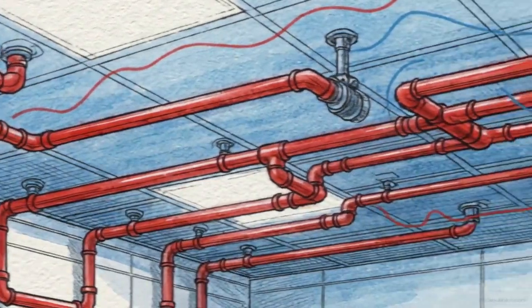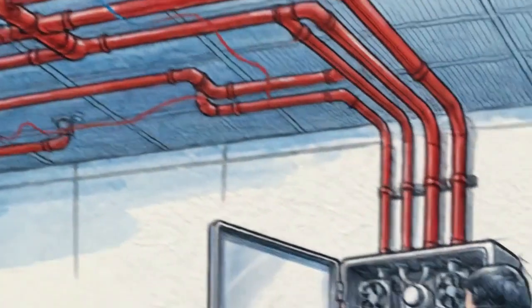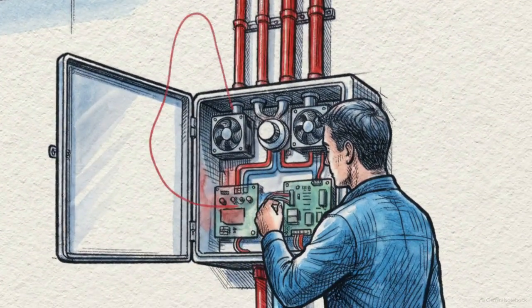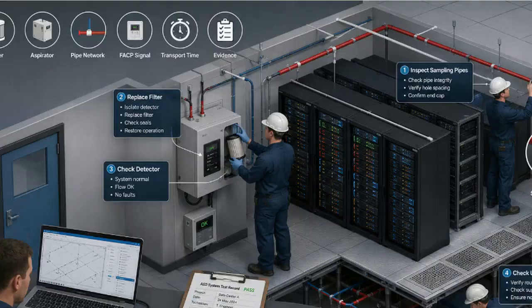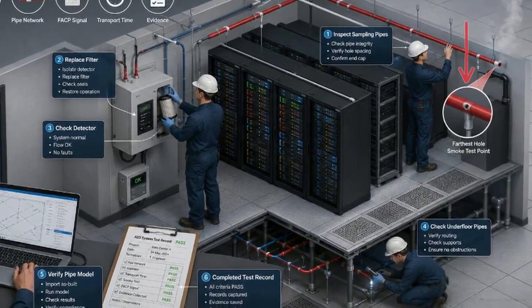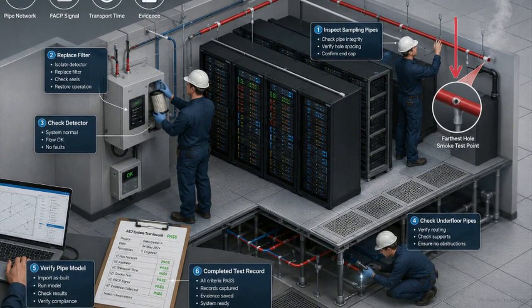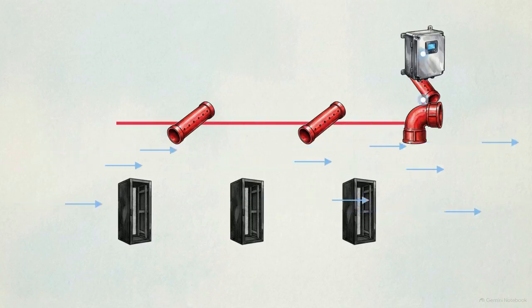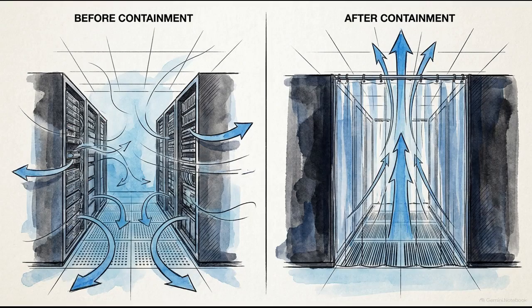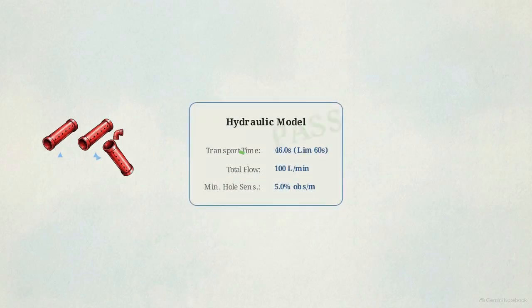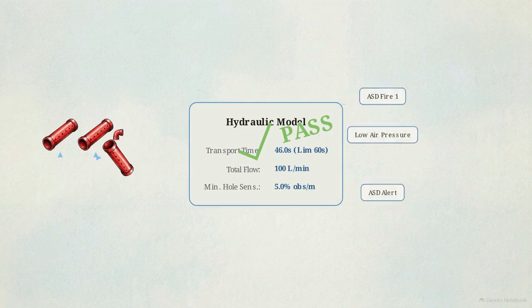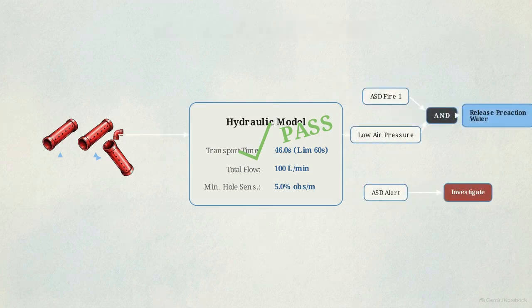Maintaining an ASD system requires a comprehensive inspection, testing, and maintenance program that evaluates the entire sampling network, not just the particulate filter. This holistic maintenance workflow includes verifying pipe integrity, simulating flow faults, and conducting routine transport time tests from the farthest sampling hole. Operators must treat ASD as a living network. Any facility modification that changes the room's airflow velocity or containment requires an immediate reevaluation of the sampling pipe model. Early smoke detection delivers true business continuity only when its physical pipeline matches the room's aerodynamics, its hydraulic math is proven in the field, and its logic matrix enforces a disciplined operator response.